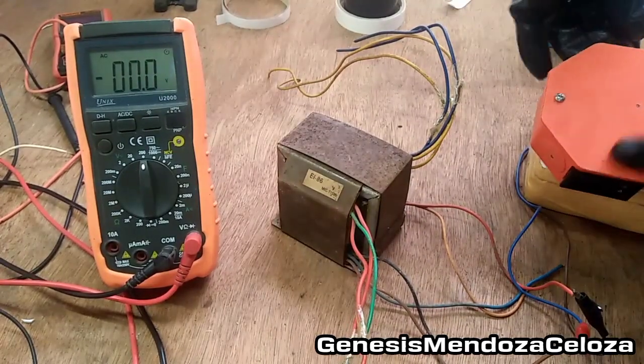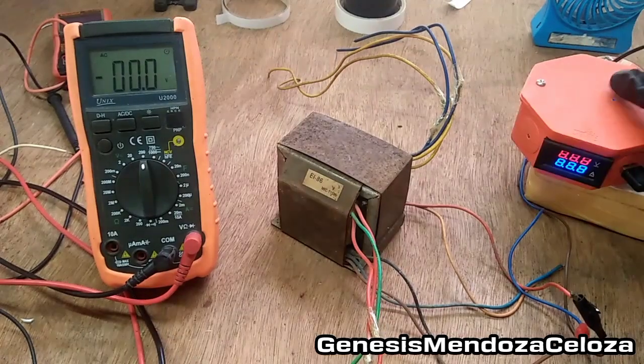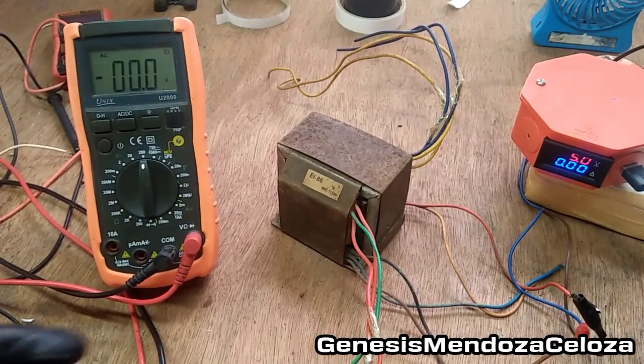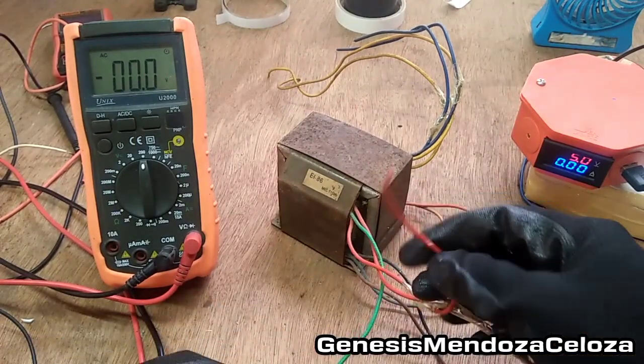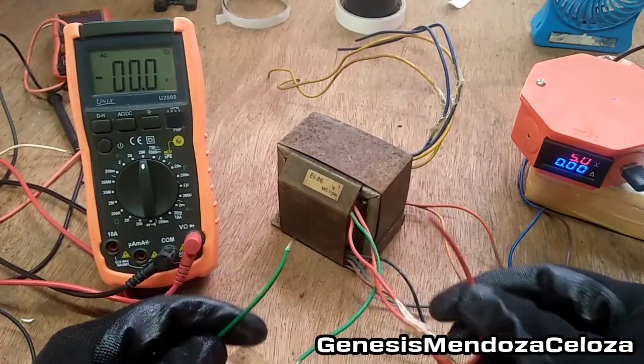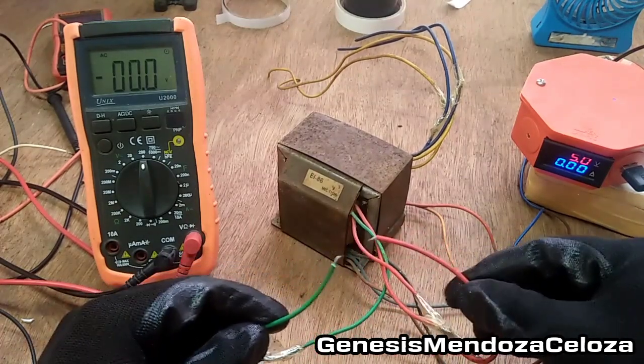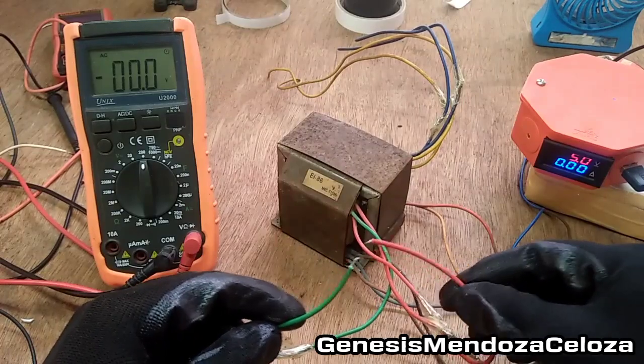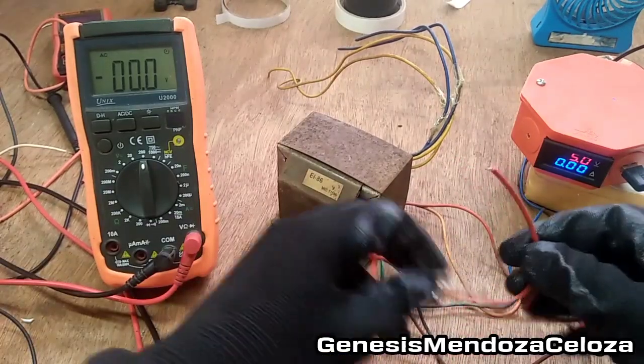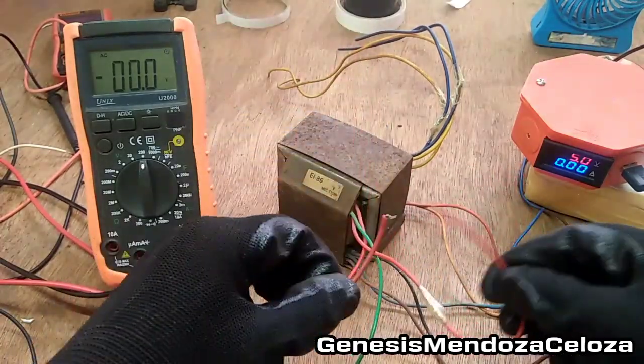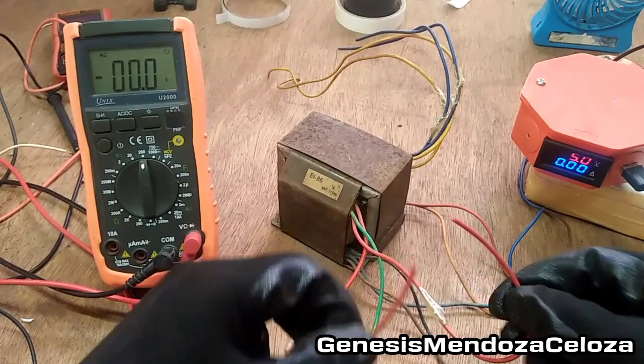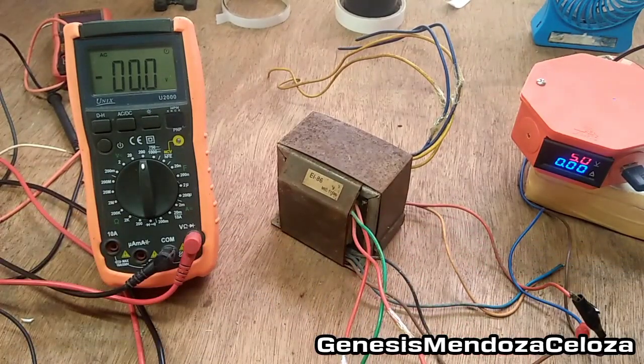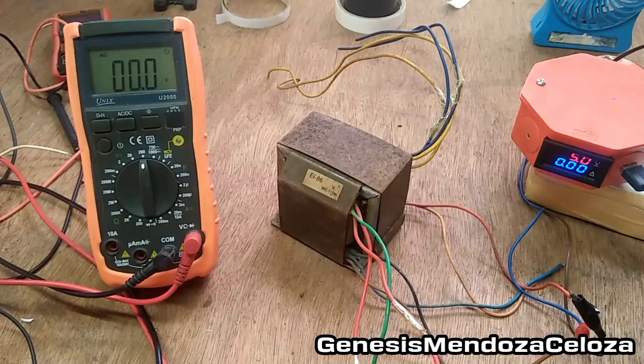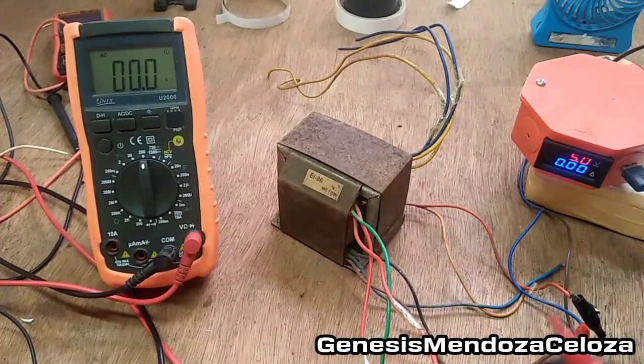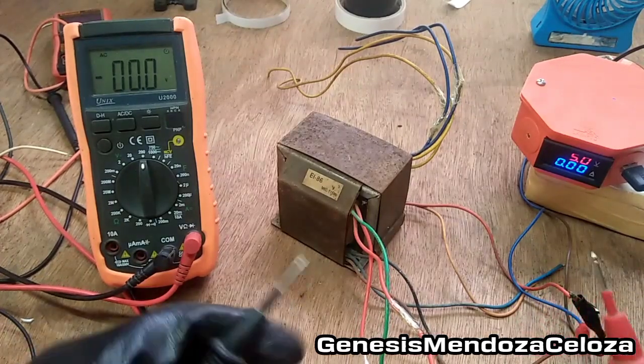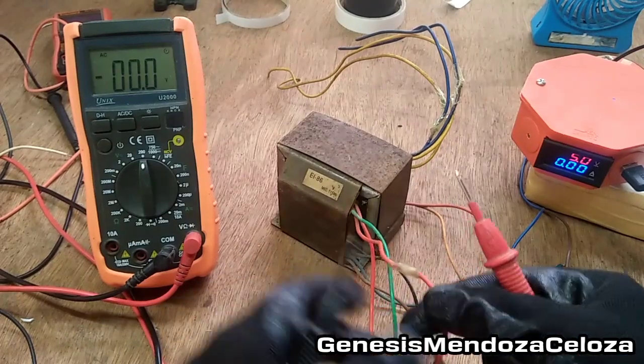An isolation transformer is just a big old style AC line transformer into which you can plug your device. The transformer has a 1-to-1 voltage ratio, so it doesn't change the power in any way, but it isolates it from the AC line, making service of switchers a lot safer.